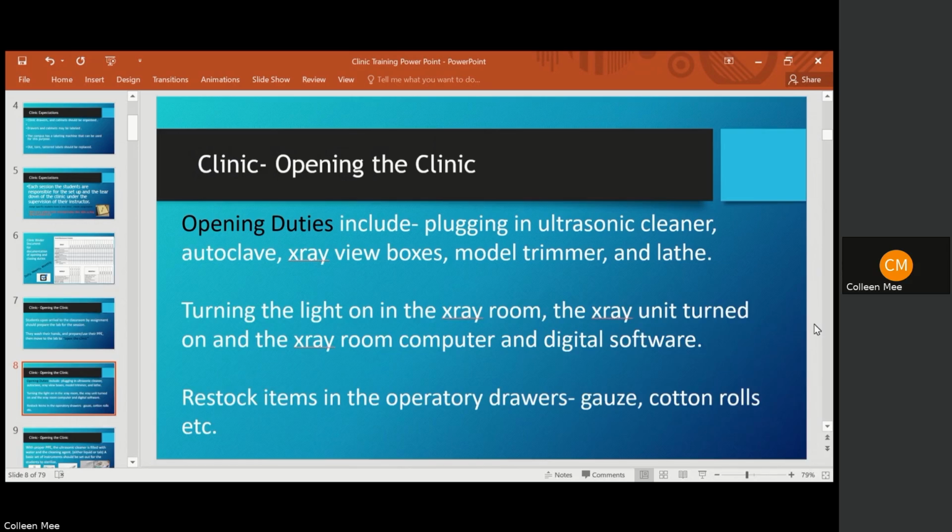There are maintenance instructions that come in the user's manual with your autoclaves, and they're all a little bit different, but please make sure you've read through them to make sure that you are following the directions specific to your unit. Many of them will say clean the door gasket with a mild detergent and wash with a sponge every day. All right, that's what this one says. Weekly, clean the air jets, and it tells you how to do that. Put some oil in the door pins. I mean, how many of us are doing that? So I want to remind you, please, please look at your owner's manuals.